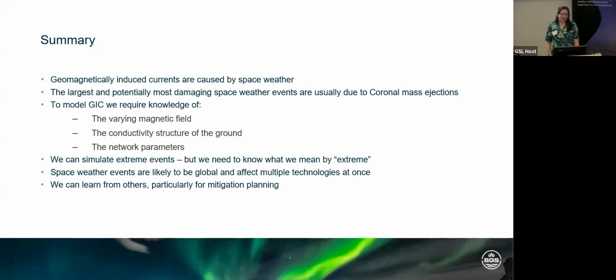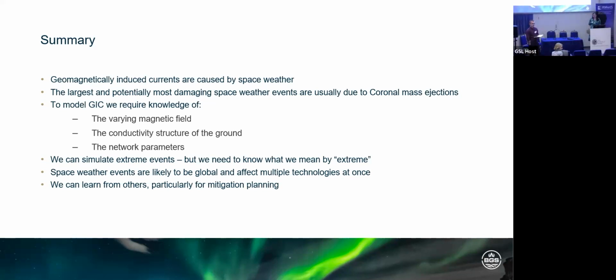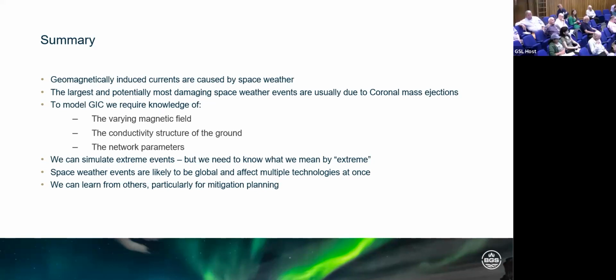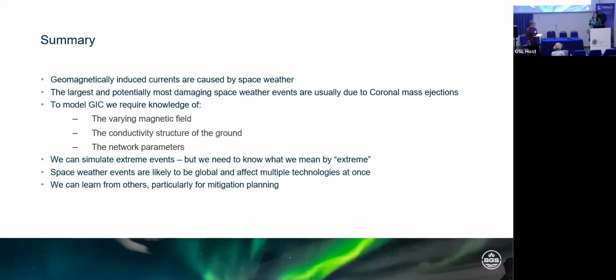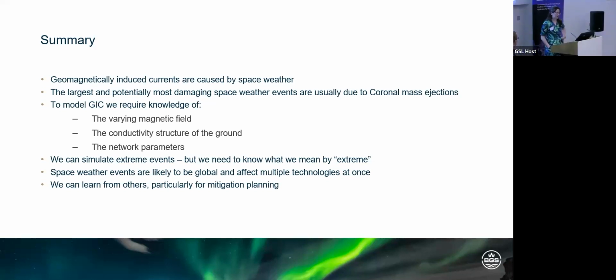But it's kind of the first time they've really put numbers on it that are so openly accessible that we can actually run it through our model and say that transformer might be experiencing that amount of current for that amount of time. A per unit figure would probably be more useful for people - percentage of the transformer capability. I can ask whether it's possible to get some kind of per unit or percentage type figure back, but it's not my area of expertise, I have to admit.